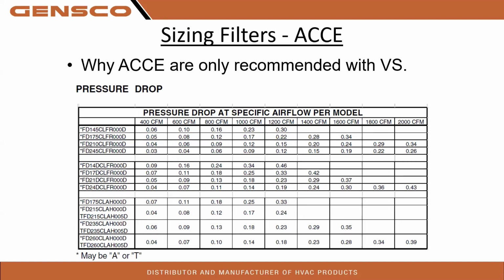This is important because these are great for filtration, but look at this pressure drop on these. We get a lot of them where they're doing an FD17 on a 4-ton and a 5-ton system. You don't even have ratings on here, so you can't use them for 4-ton and 5-ton. So this is a good chart to see what you can actually use on those 5-ton systems. You want to put in the biggest possible, because look at this 0.39 pressure drop. So you definitely want to oversize these as much as you can to get good filtration and good airflow.